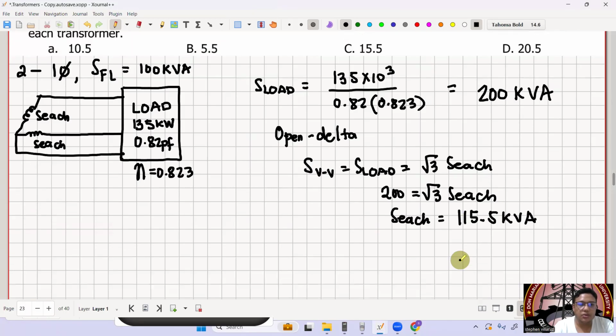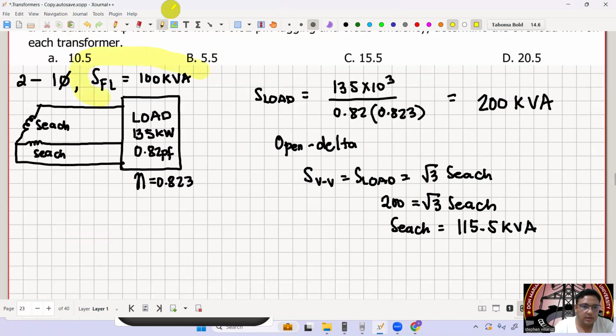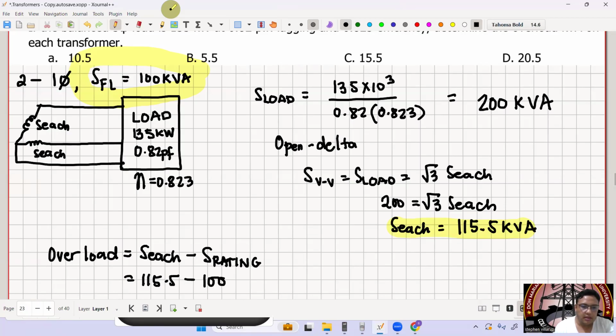Okay? So ngayon, as you can see, yung rating natin dito is 100 lang. Okay? Versus so dun sa rating natin in open delta. So there is an overload here now. So yung overload natin is equal to yung ating S each minus yung rating ng kada isang transformer. So therefore, this is now 115.5 minus 100. And this is now equal to 15.5 kVA. Letter C. Okay? Next tayo, number 24.